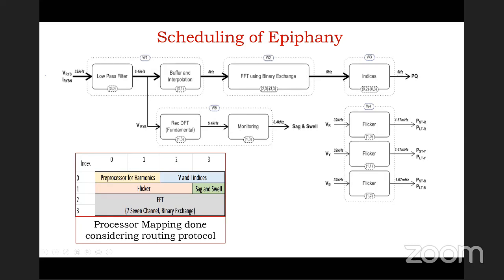So in the cycle, 5 hertz is what we will be getting, meaning 1 by 5, basically every 0.2 seconds, that's how we get the data out from it. Similarly, sag and swell monitoring requires the complete 6.4 kilohertz.